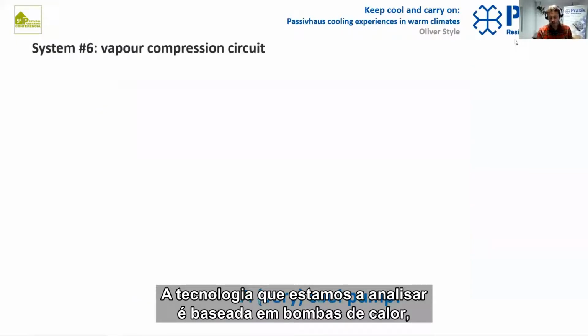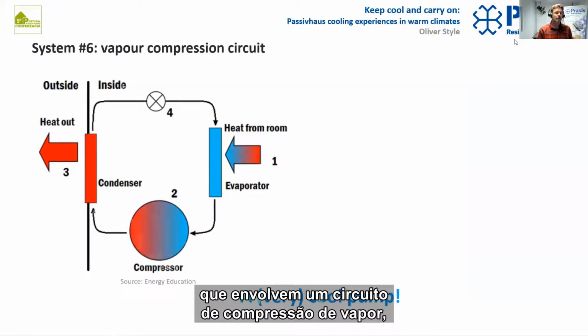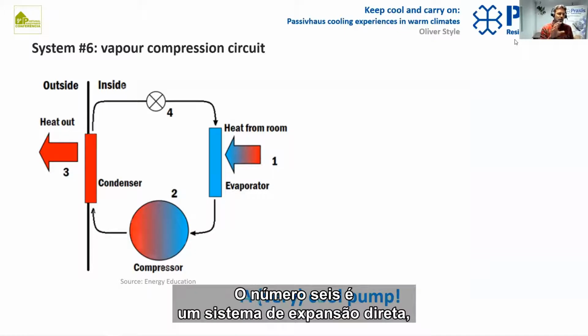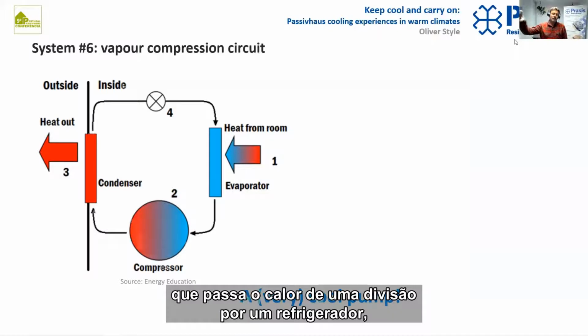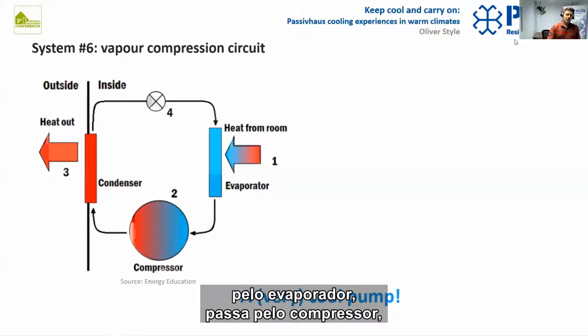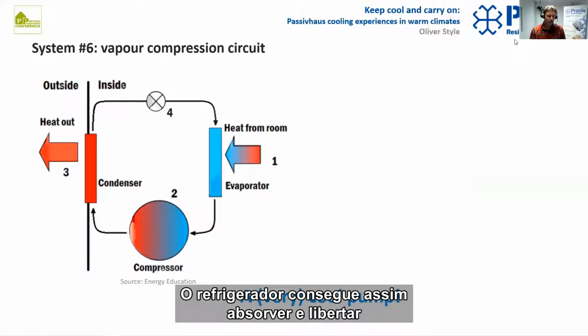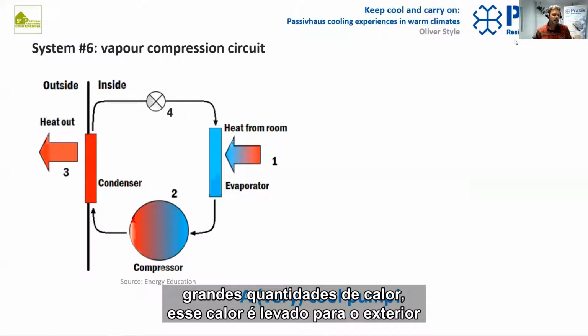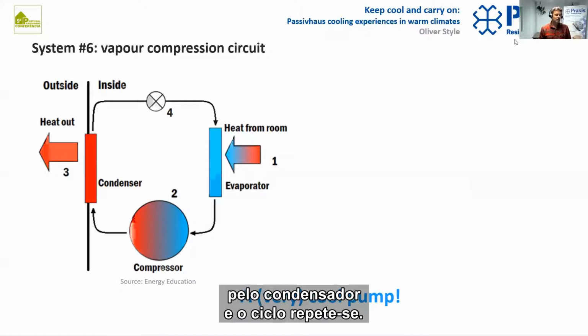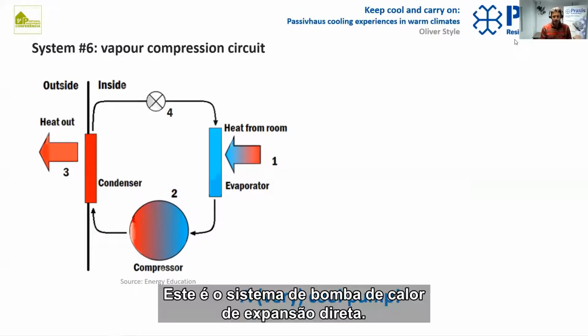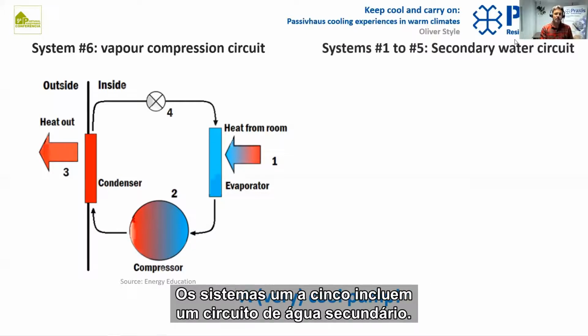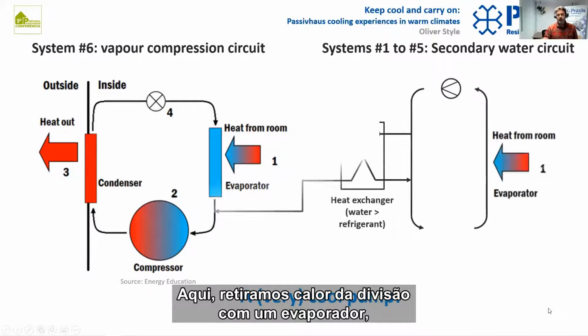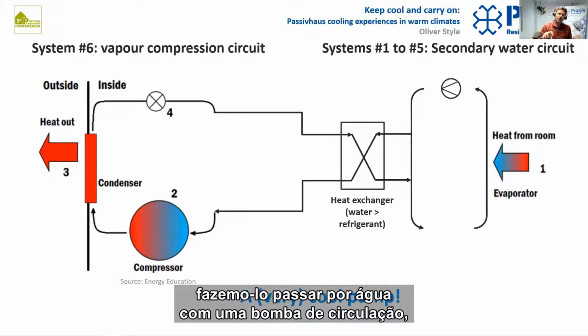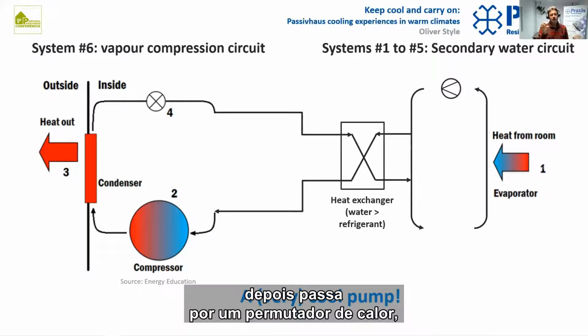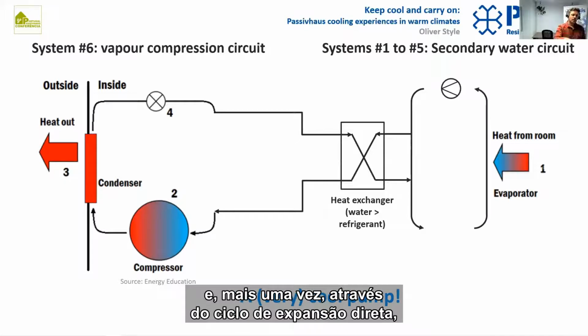So the technologies we're looking at here are all based on basically heat pumps involving a vapor compression circuit, which is what you can see here in the image. So number 6, a direct expansion system, basically takes heat from a room, passes it to a refrigerant through the evaporator. That goes through a compressor, which changes its phase. That means a refrigerant is able to absorb and release large amounts of heat. That heat is then taken outside to outdoor air via the condenser, and the cycle is repeated. So this is the direct expansion heat pump system. And then systems 1 to 5 include a secondary water circuit. So here we're taking heat from the room with an evaporator, passing it to water with a circulating pump that then goes through a heat exchanger. The heat is taken from water to refrigerant, and then again through the direct expansion refrigerant cycle, we're taking heat outside.